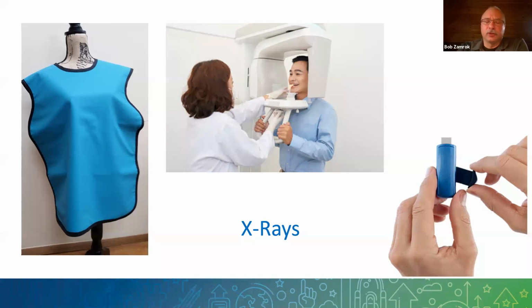On your handhelds, which are very big now too, you just want to make sure that your batteries are working well, and you want to make sure that the guard on there, the little disc, the filter, doesn't have any cracks, is in good shape, and isn't bent or anything like that. I can't really think of anything else for X-ray right now, but the cone beams really have been a big thing for us with inspections and just how they get installed and where they get installed. A lot of states are starting to get a lot more involved with where they go and how they're used.